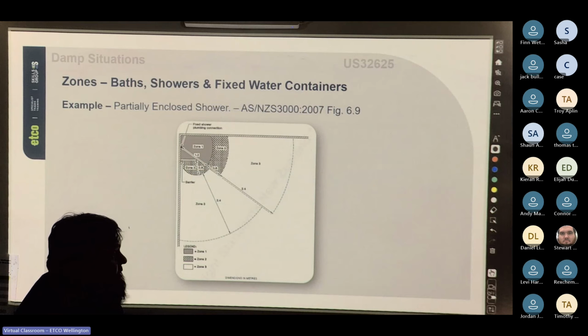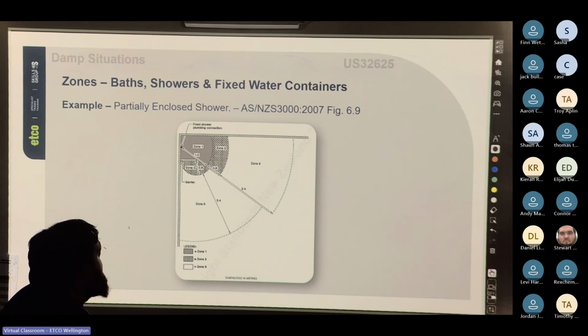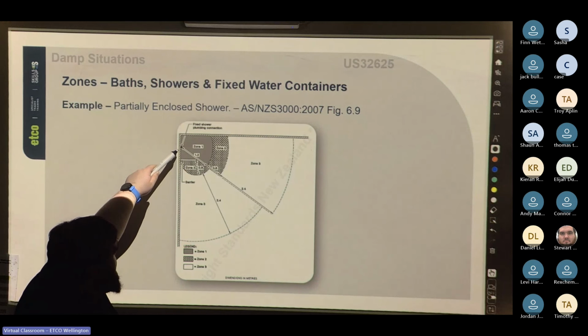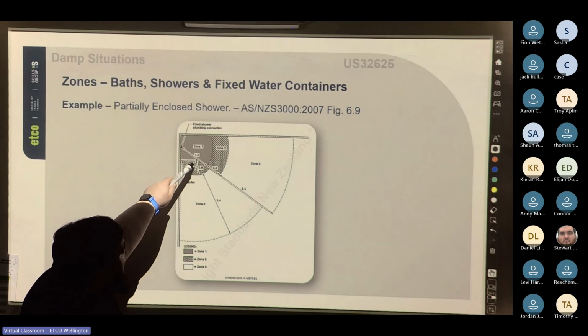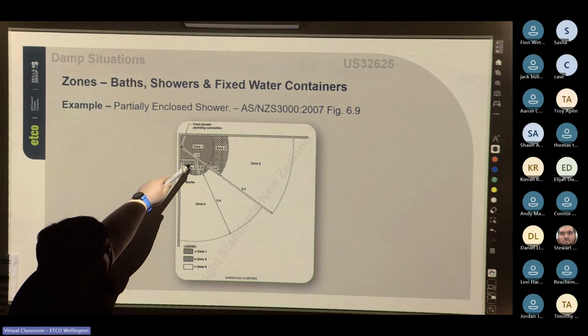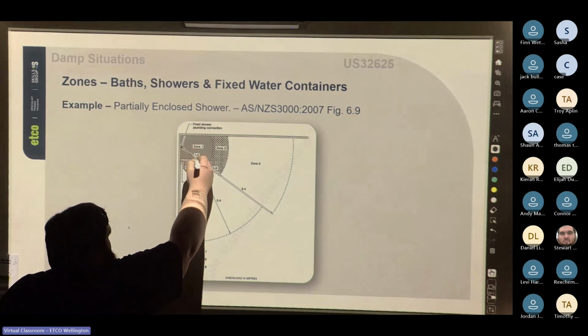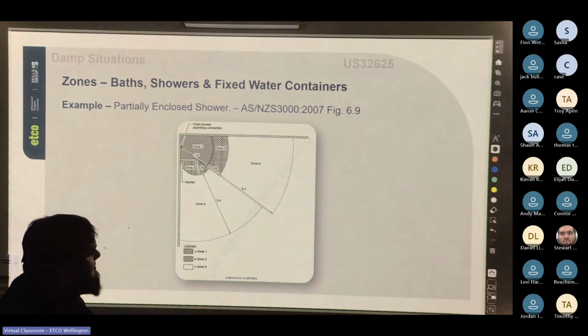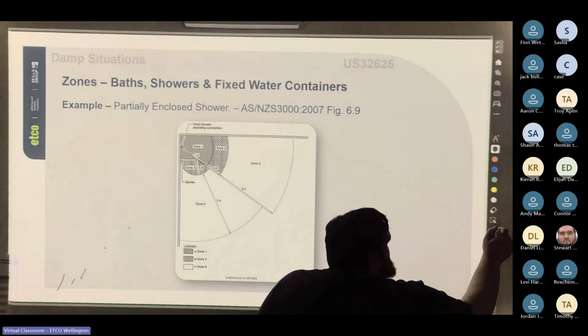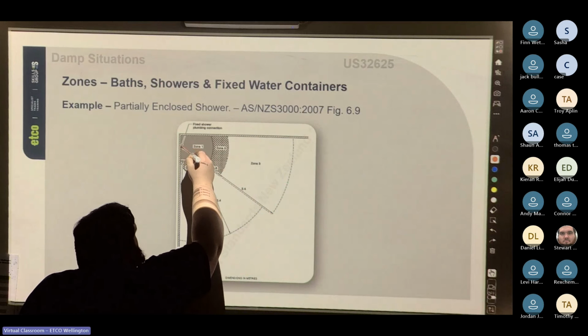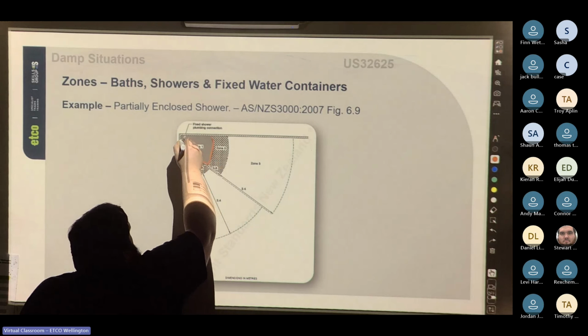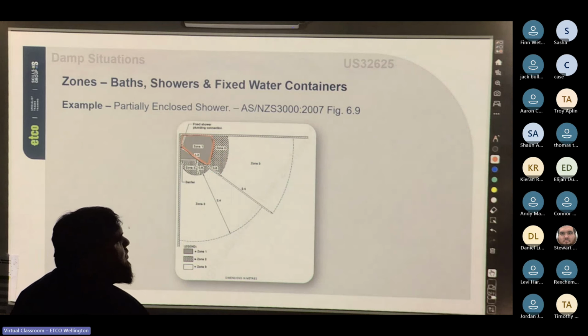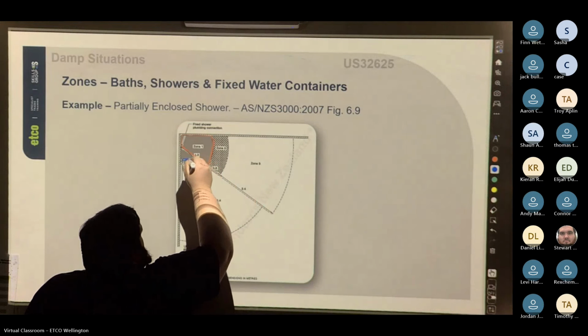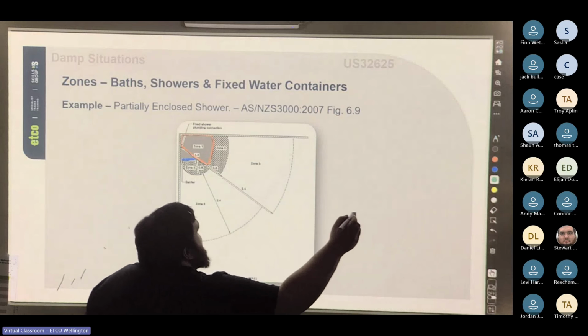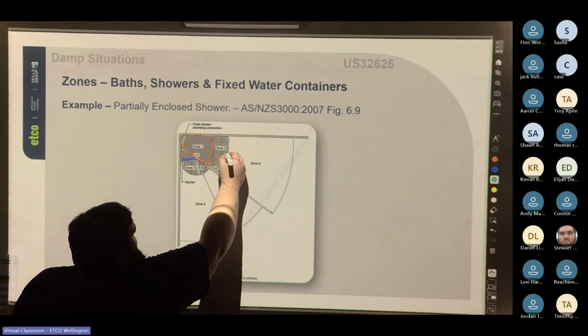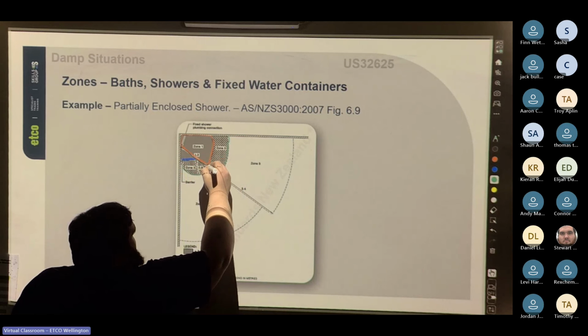Cool. And then we talk about 6.9, a partially enclosed shower. Again, from the fixed shower point we have a 1.2 line until it hits the corner of our partially enclosed shower. That's where you can see there's this line here and it stops there. I'll draw it in a different color. So you've got this area here. That is our zone 1, and because it hits this wall here, it changes trajectory and gets cut off. Then we can draw our zone 2, which is 0.6 meters from zone 1. It follows that same hard line.